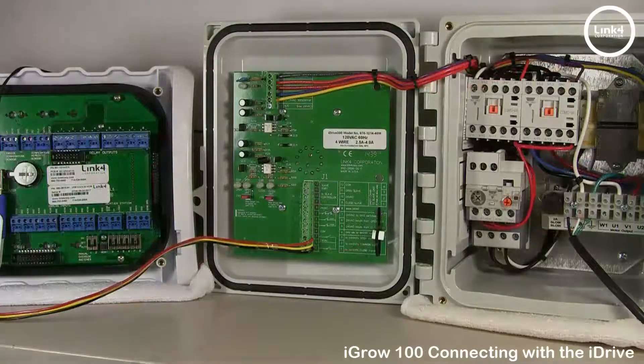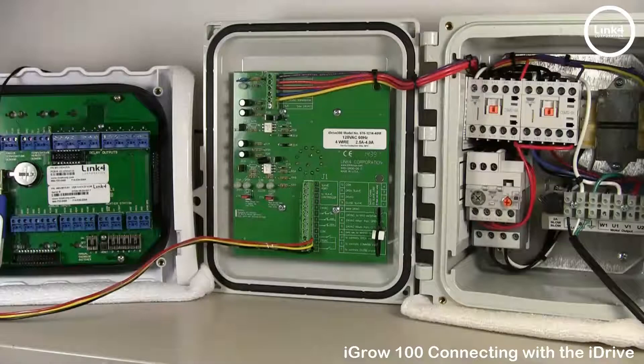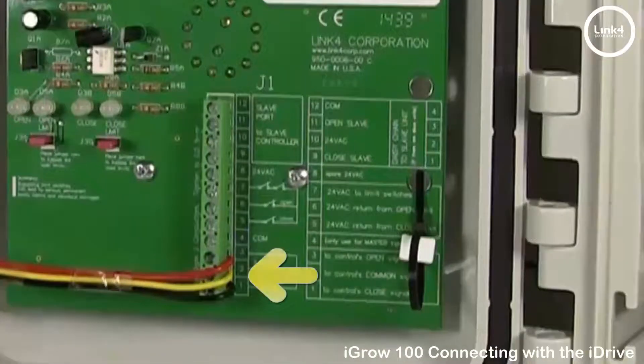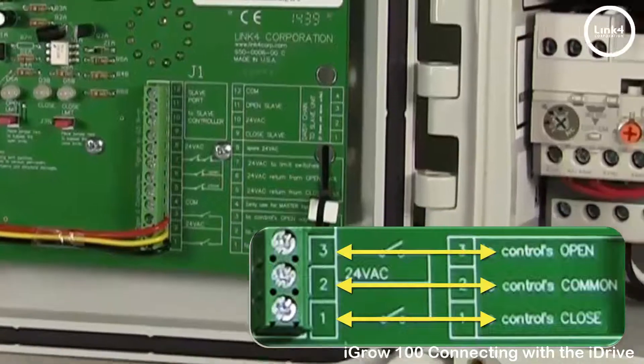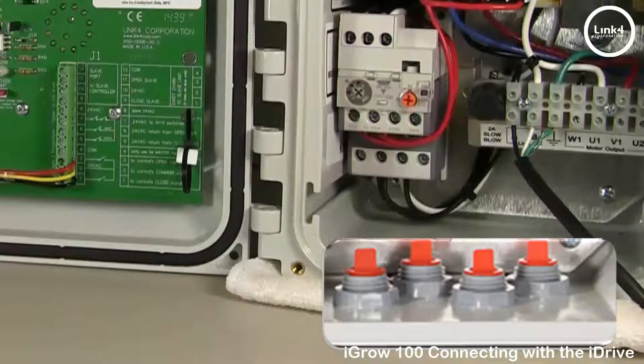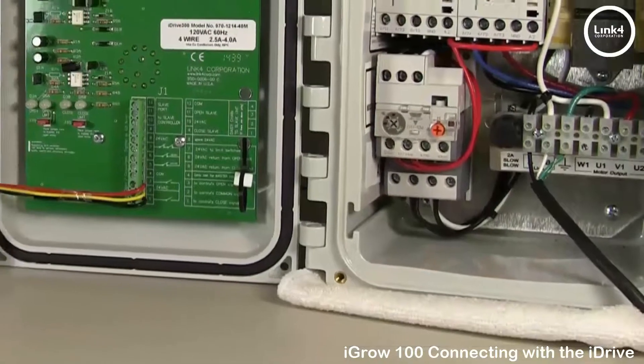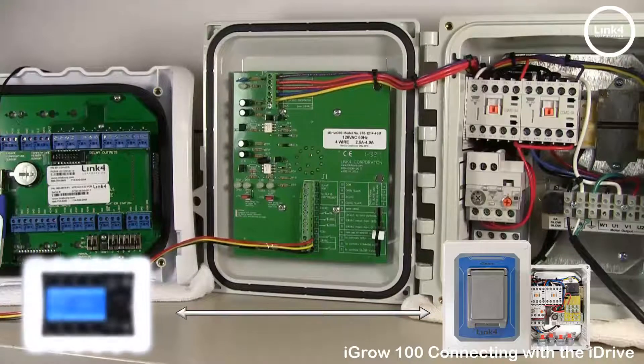On the iDrive J1 portion of the printed circuit board, located in the lower right corner on the back of the iDrive door, locate: one, the control close signal; two, the control common signal; and three, the control open signal. At this location, land your three-wire strand, run it through the bottom of the liquid-type connectors, and continue your wire run towards the iGrow 100 series controller.